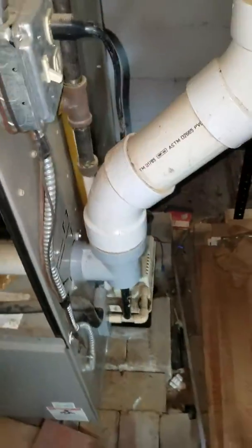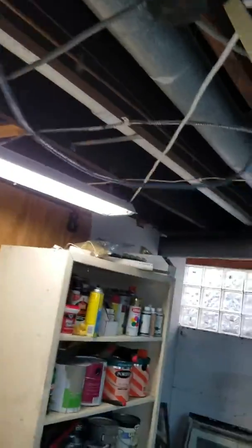It is a 96% 3-inch flue that runs up, turns — so 1, 2, 3 elbows — runs all the way out and comes out to the side right here. It is 3-inch all the way through.